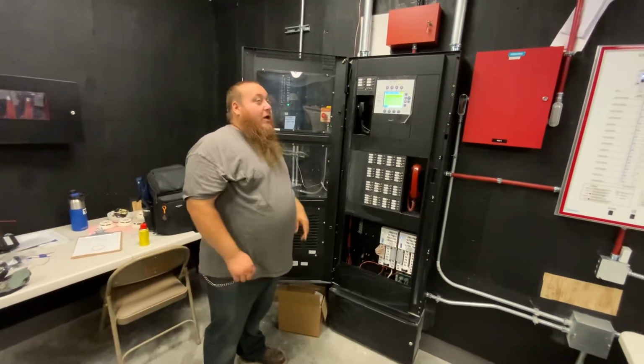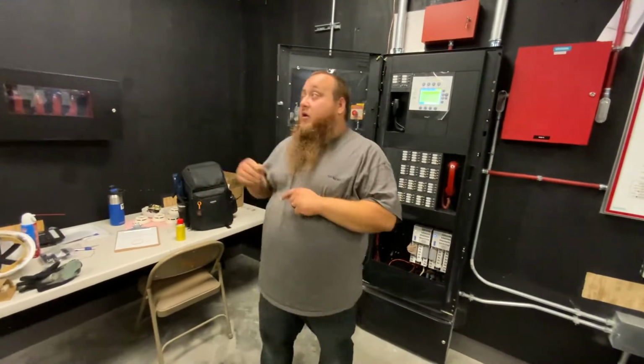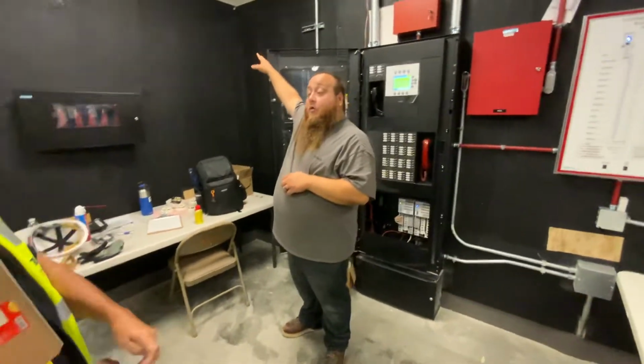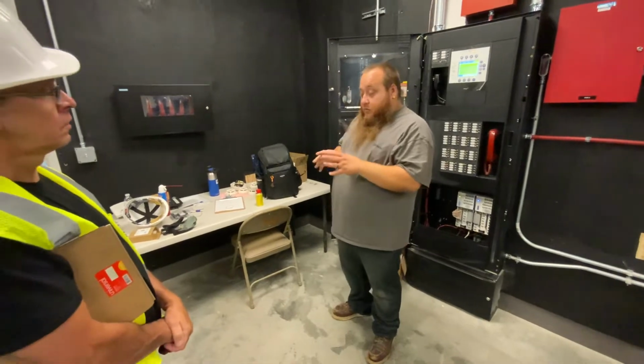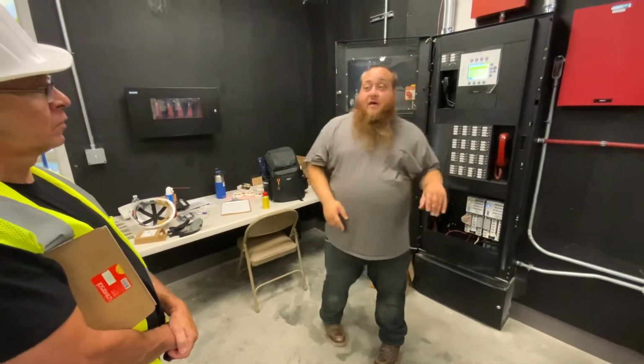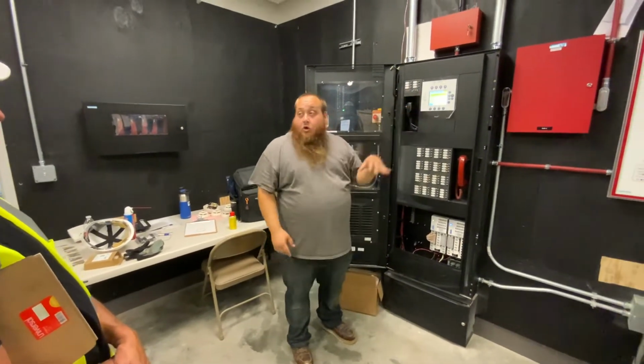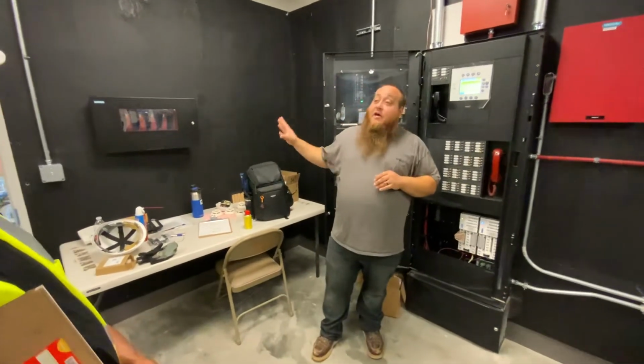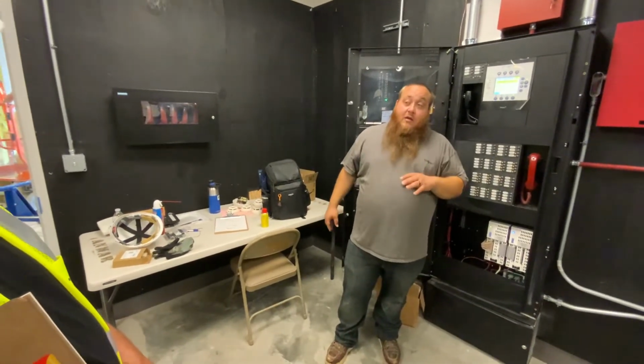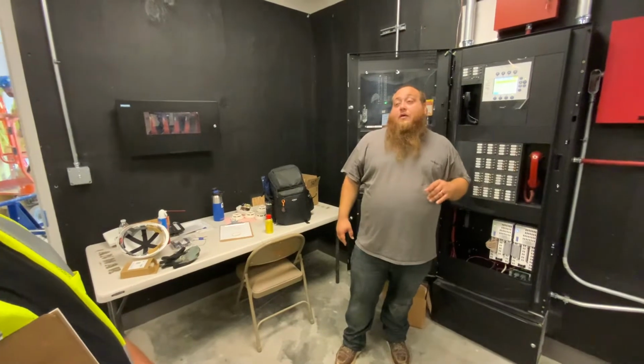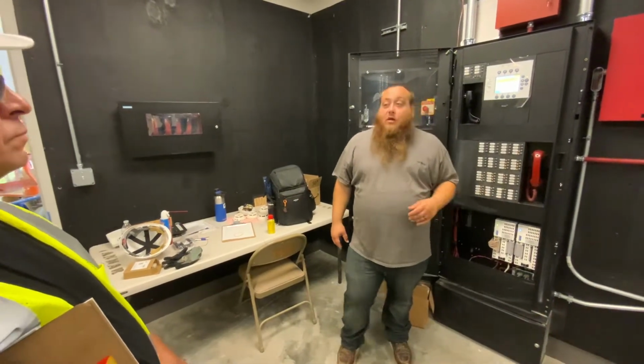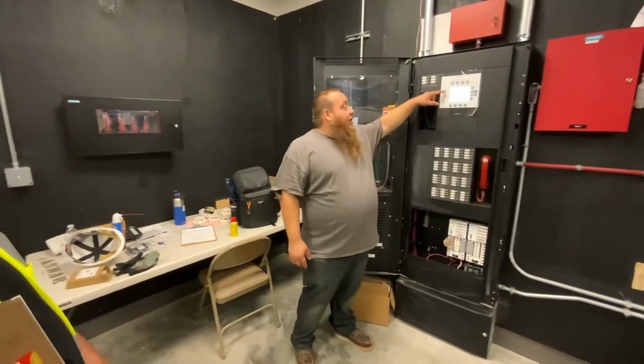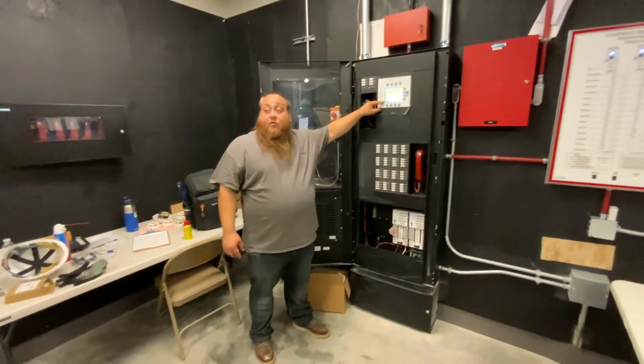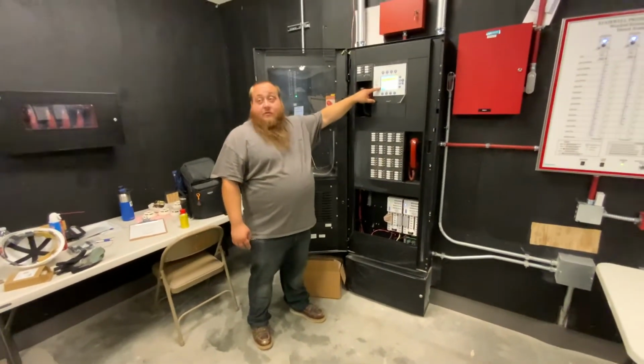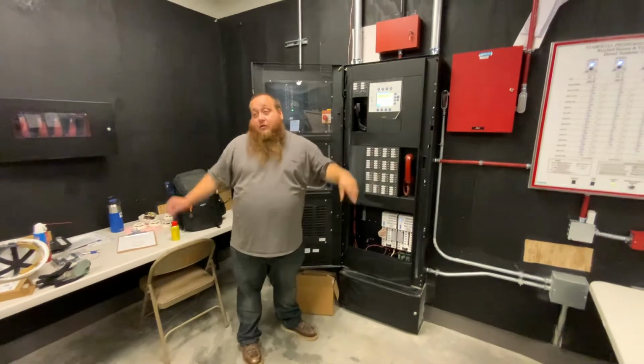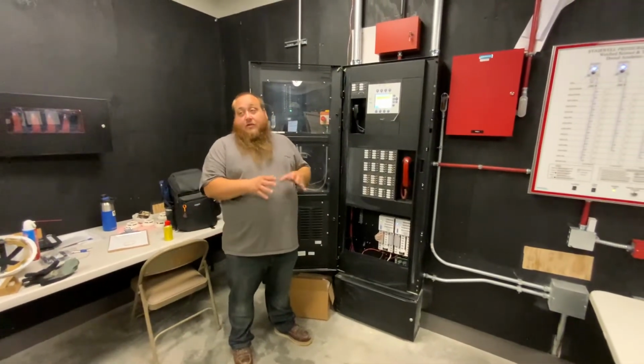You also have an annunciator at your front entrance. That annunciator only has simple functions, it doesn't have bypasses and things like that. You're able to acknowledge and silence from there, and reset, but you're not going to be able to disarm anything or take anything out. All that's going to do is allow you to see all the messages here as well. Whatever's displaying on this system will also display on your annunciator, you just have very limited control there.